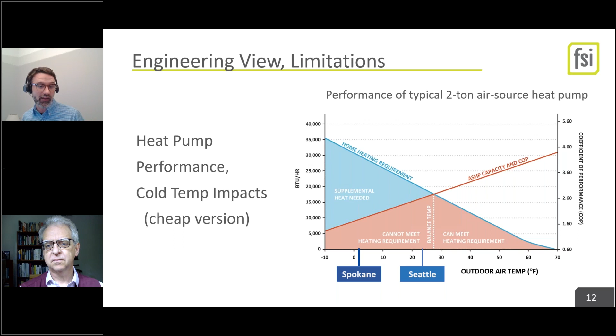These are Daikin, but you could get the same curve from Mitsubishi, LG, so on. They have now done these inverter-driven compressor technology that will run down to darn near the coldest temperature you can get anywhere in Washington State, including that more cold northeast corner, without electric resistance backup. So if you're already going to have air conditioning in your building, you already have the power to run these heat pumps. These are VRF, but remember that same form factor, you can get them in vertical package units. Only one manufacturer right now. You can get them in PTAC versions with 2 little through the wall penetrations instead of the big box. And look, even in Spokane, the COP is above 2.5. Another way to say that again is 250% efficient.